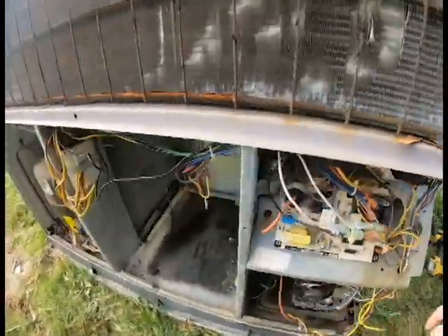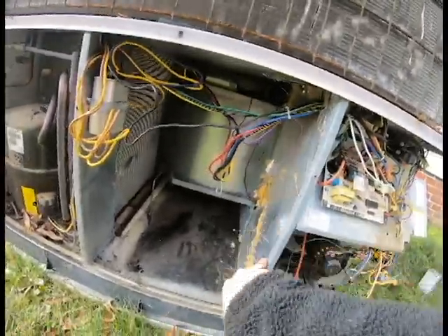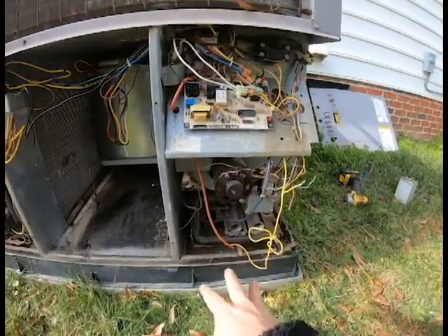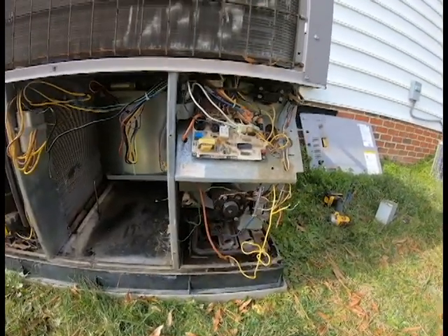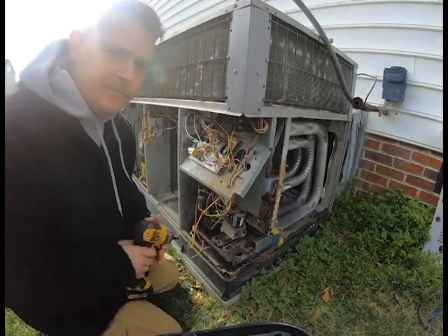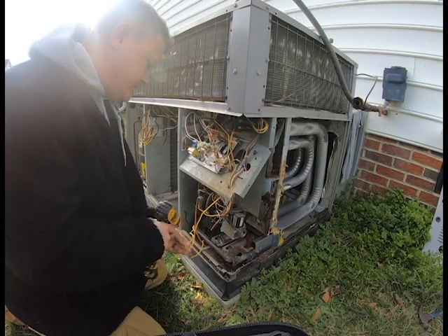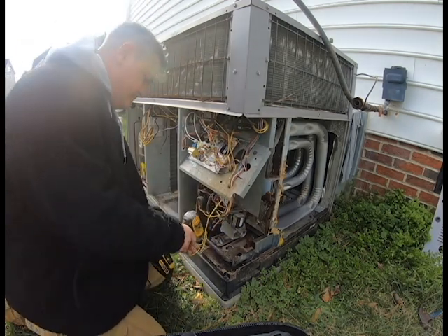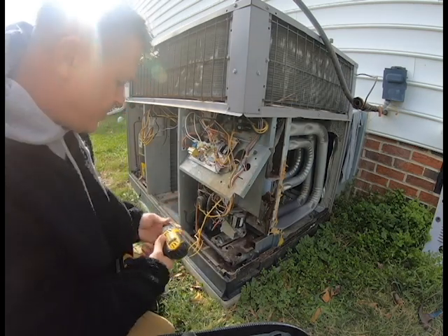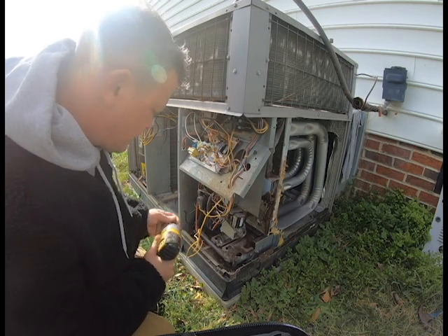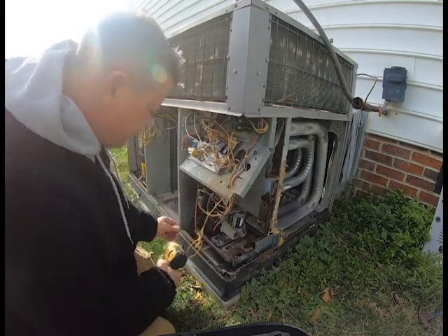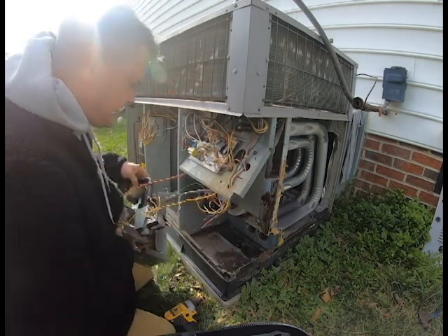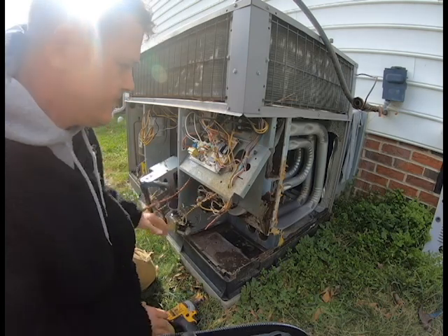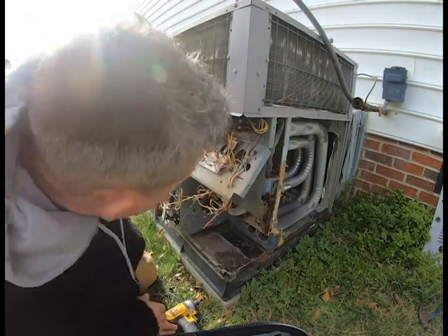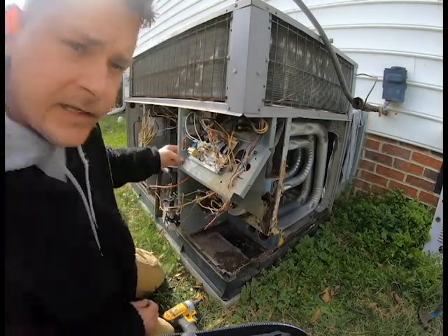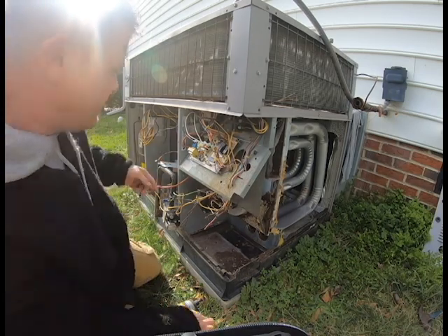So we got everything off now. Now we've got to remove everything attached to this bracket here and our burners, so we can set those over. All right guys, I try to set it up so you can see everything. First we're going to remove our burners - here's the screw for our burners, and we have to take off our ground screw here. Now with that, we can take our burners straight out and set those over to the side here. Next we want to remove this panel, which is connected by screws on the opposite side over here, so I'm going to remove those.